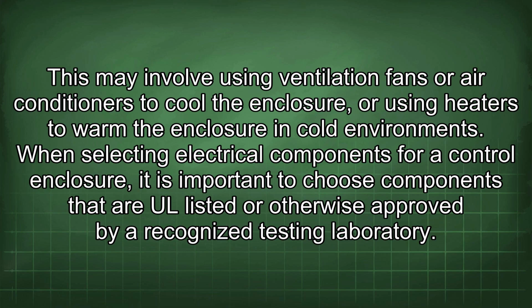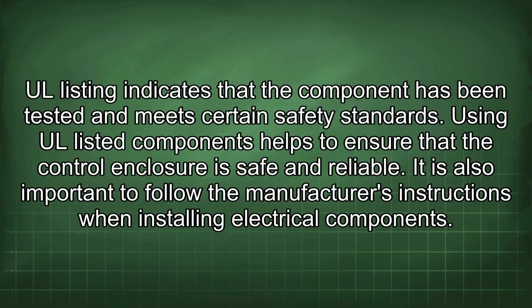When selecting electrical components for a control enclosure, it is important to choose components that are UL listed or otherwise approved by a recognized testing laboratory. UL listing indicates that the component has been tested to meet certain safety standards. Using UL listed components helps to ensure that the control enclosure is safe and reliable.